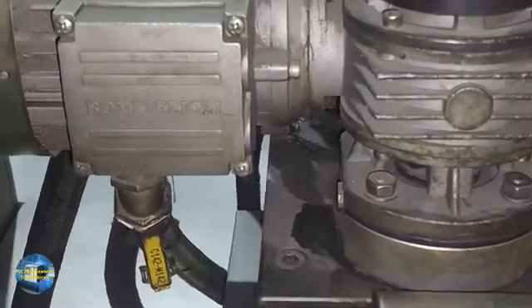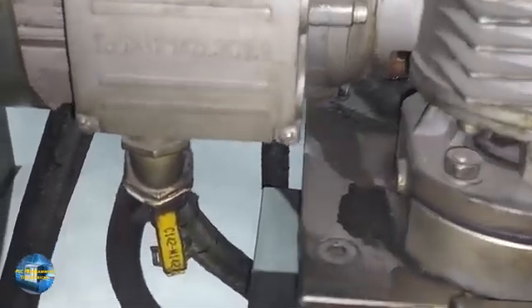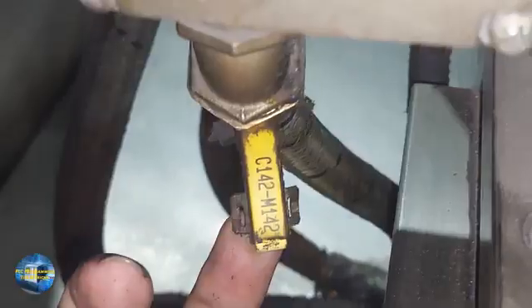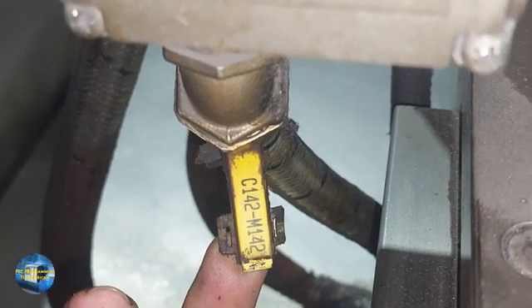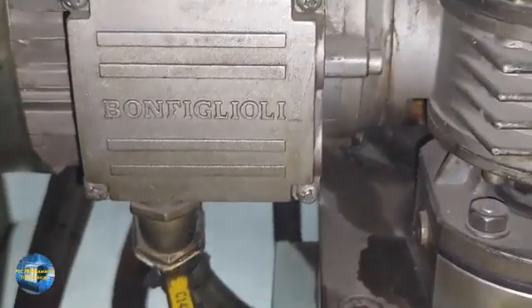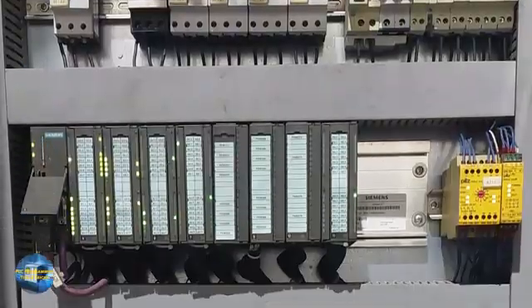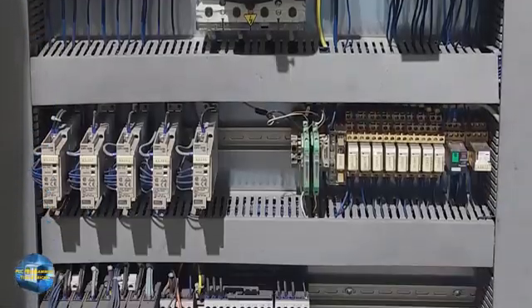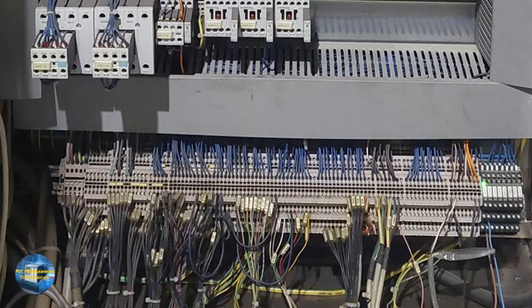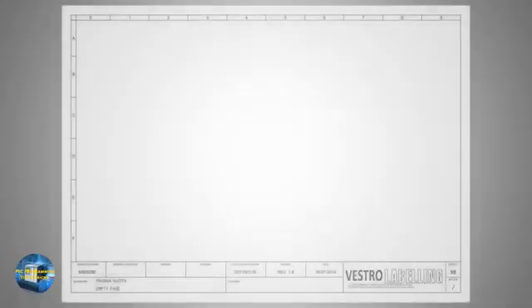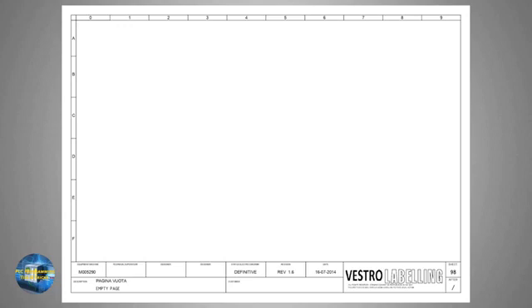For example, if we have a motor installed in the machine and if you look closer, we have a tag attached to the cable of the motor with M142 mentioned on it. Now the question is where this cable is connected in the machine electrical panel and how the PLC is controlling this motor. For this we need to understand how to read the electrical diagram.